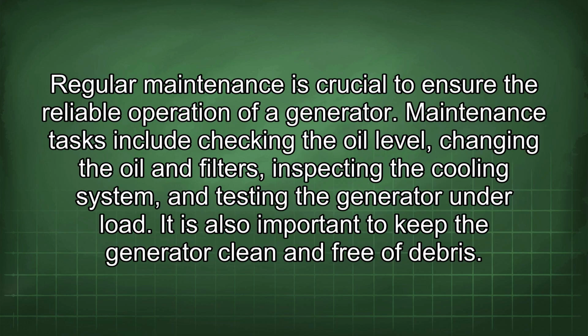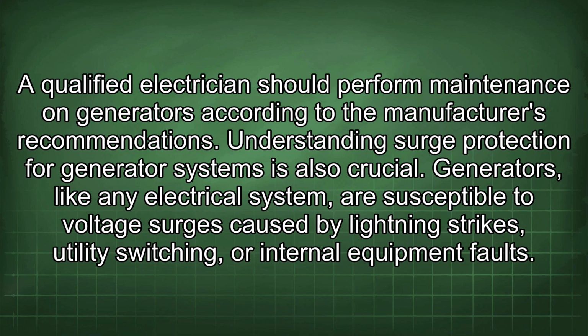Regular maintenance is crucial to ensure the reliable operation of a generator. Maintenance tasks include checking the oil level, changing the oil and filters, inspecting the cooling system, and testing the generator under load. It is also important to keep the generator clean and free of debris. A qualified electrician should perform maintenance on generators according to the manufacturer's recommendations.